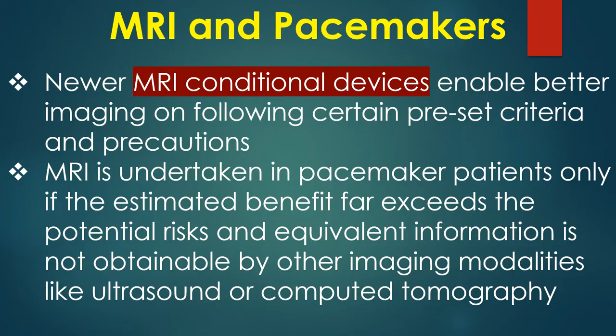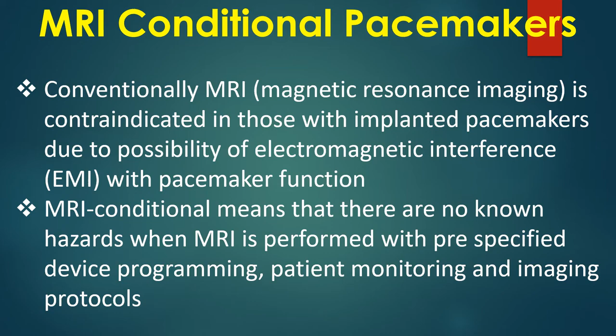Discussion on MRI conditional pacemakers including safety of 1.5 Tesla and 3 Tesla MRI scans. Conventionally, MRI is contraindicated in those with implanted pacemakers due to possibility of electromagnetic interference with pacemaker function. MRI conditional means that there are no known hazards when MRI is performed with pre-specified device programming, patient monitoring, and imaging protocols. MRI conditional pacemakers were first introduced in 2008.